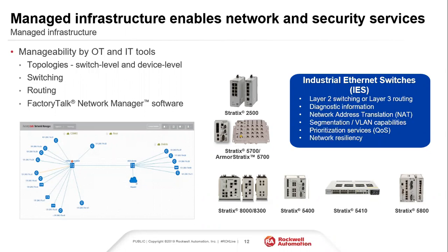So some of the benefits that you get here, like I said, you get diagnostics. You also have the ability to see the topologies. So if I get diagnostics, I can also tell you what's connected to it or where it's going. As I connect multiple switches together, or I connect the switch to, let's say, ControlLogix or CompactLogix, I now have tools in place that can tell me everything that's there and even give me asset information if I want. So there is a huge benefit on that end when you're looking at managed switch technology.